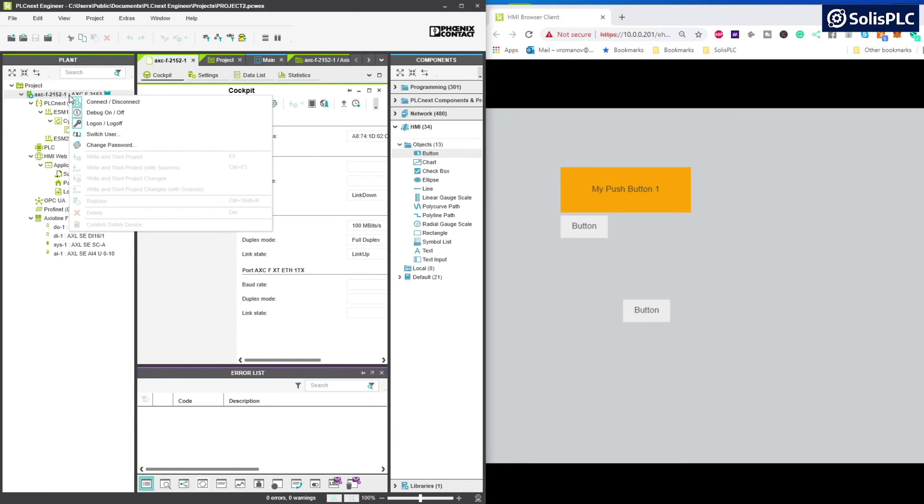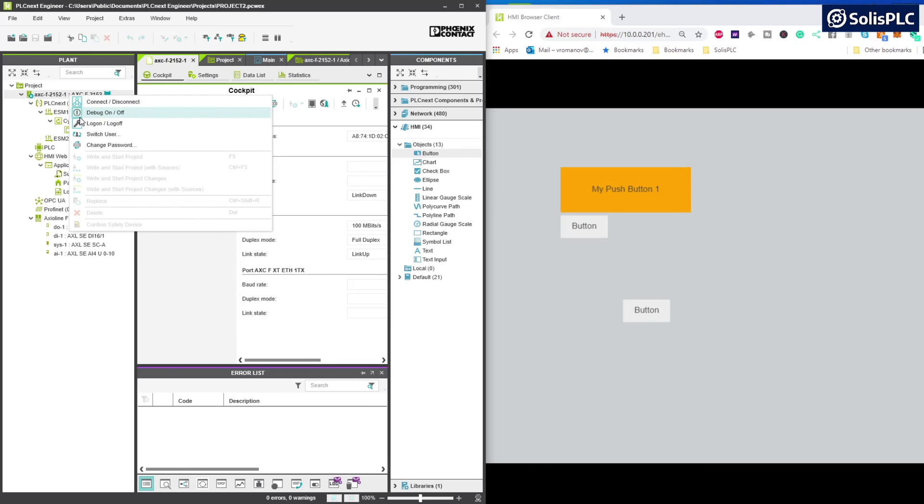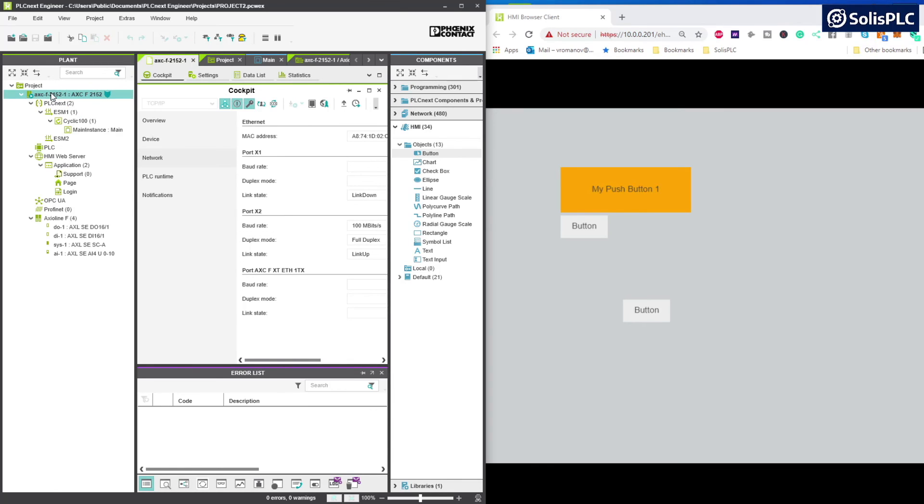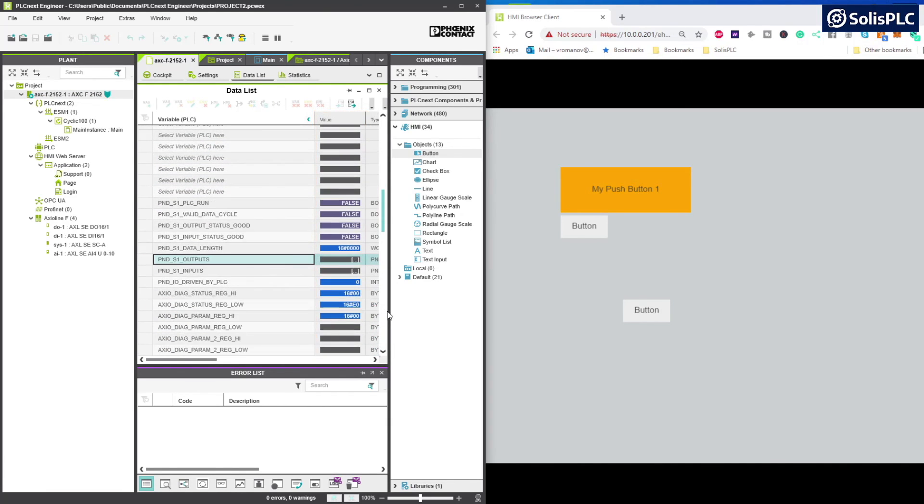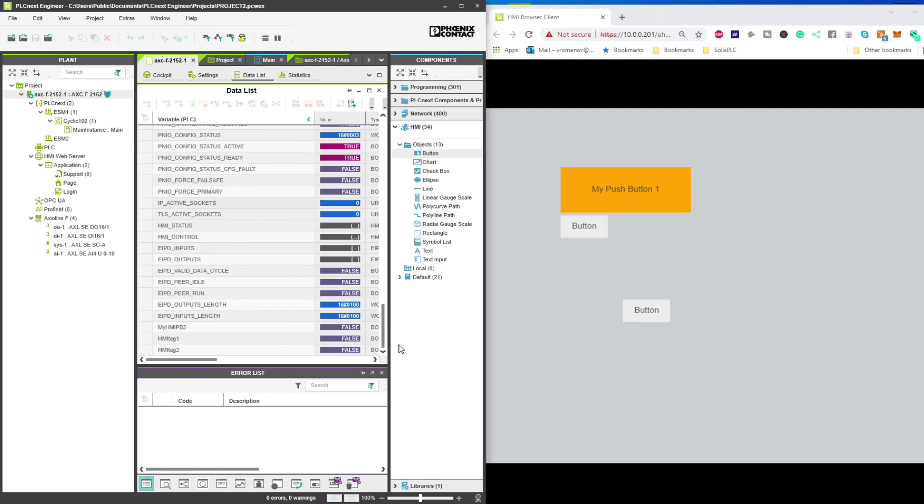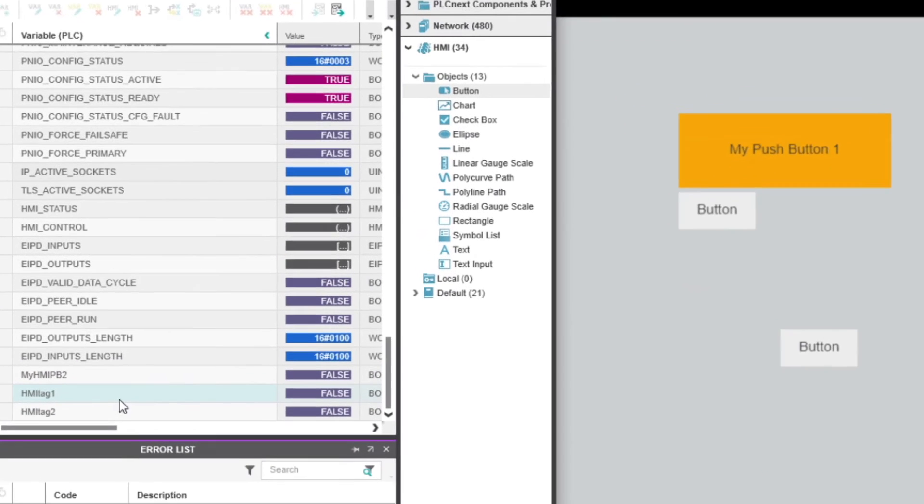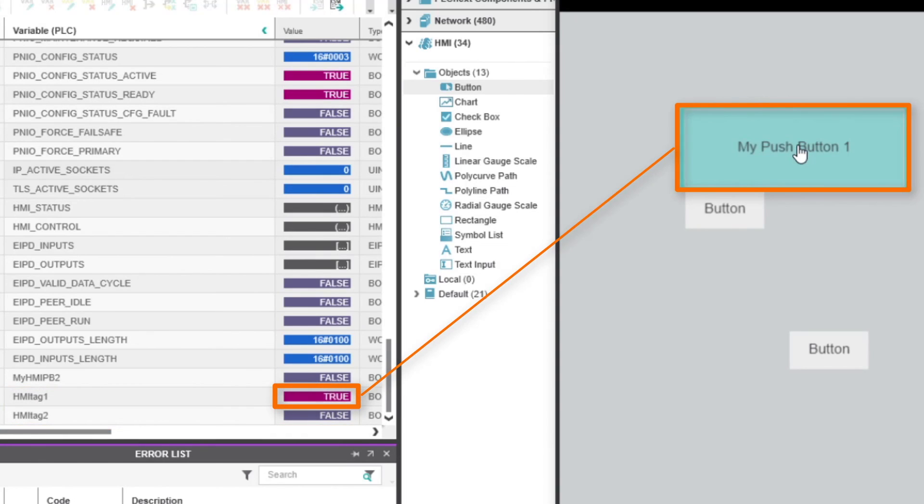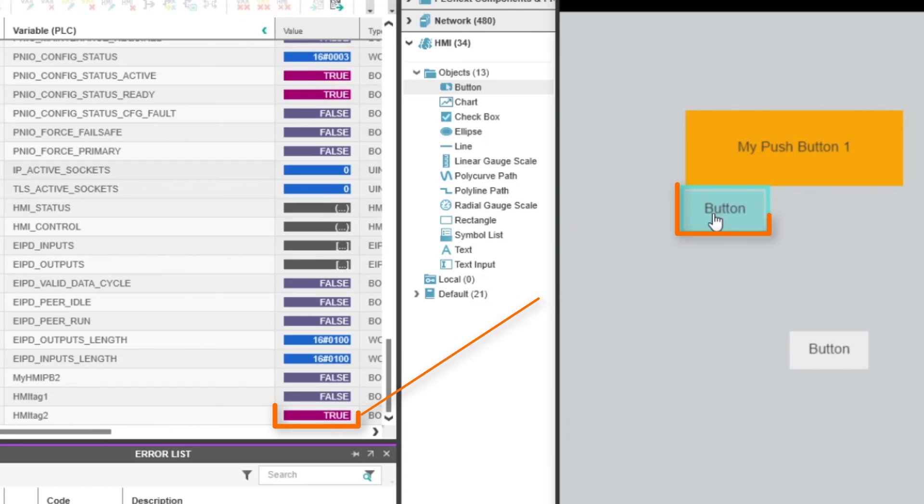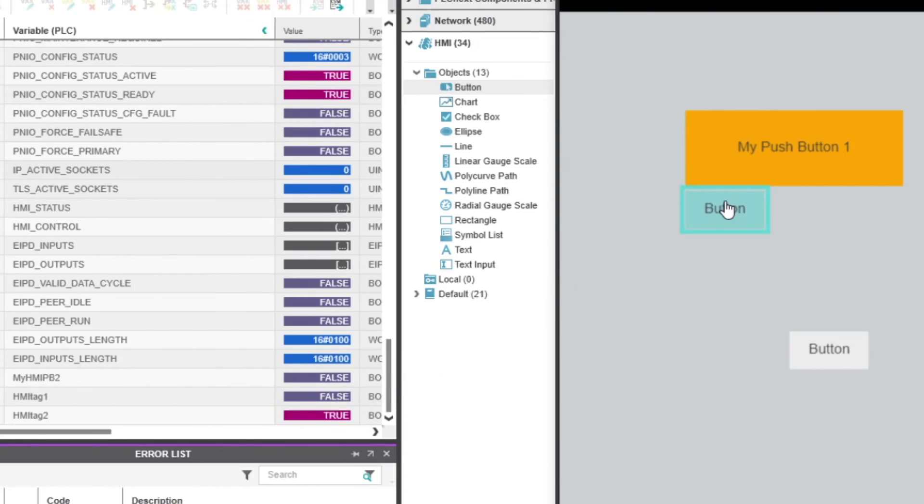What we need to do is if we right click this, we need to make sure that debug on/off is enabled, make sure that there is a blue icon around the eye. By doing that we can double click our PLC project, navigate into the data list, and you'll notice that there's tag specific values for each tag that is currently being activated. Scrolling down to HMI tag one and two, we're going to notice that as soon as I press the HMI push button that tag value is changing from false to true. That's exactly the behavior we would expect, and at this point we can create some PLC logic that's going to react to the push buttons that we're pressing.